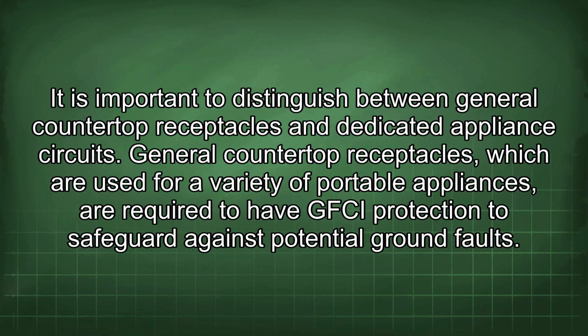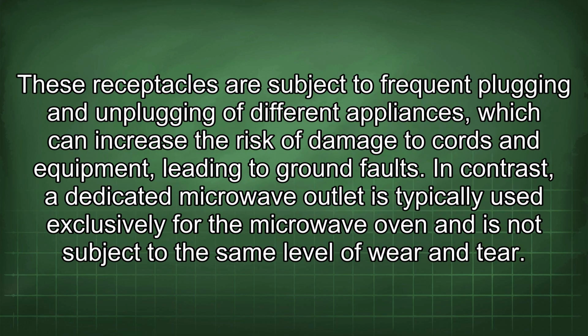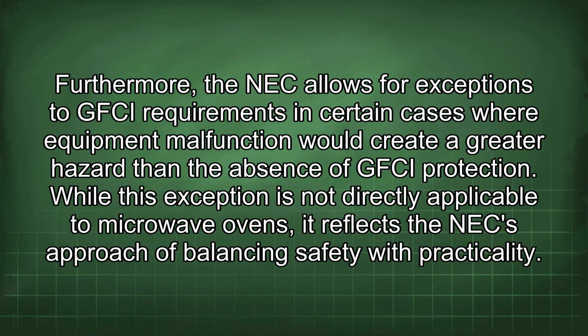It is important to distinguish between general countertop receptacles and dedicated appliance circuits. General countertop receptacles, which are used for a variety of portable appliances, are required to have GFCI protection to safeguard against potential ground faults. These receptacles are subject to frequent plugging and unplugging of different appliances, which can increase the risk of damage to cords and equipment, leading to ground faults. In contrast, a dedicated microwave outlet is typically used exclusively for the microwave oven and is not subject to the same level of wear and tear. Furthermore, the NEC allows for exceptions to GFCI requirements in certain cases where equipment malfunction would create a greater hazard than the absence of GFCI protection. While this exception is not directly applicable to microwave ovens, it reflects the NEC approach of balancing safety with practicality.